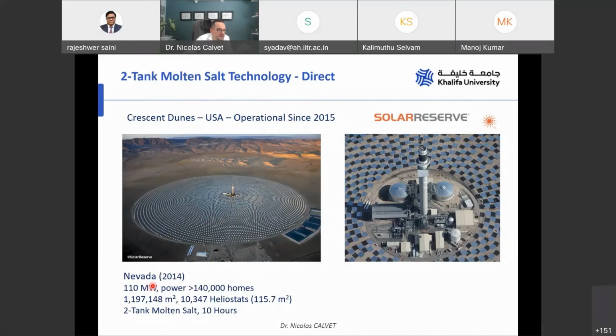I think we have now reached the limit for Power Tower, because if you look at the configuration of the plant, the last heliostat is very far away from the bottom of the tower, maybe more than 1 kilometer, maybe 2 kilometers. And so it's very difficult to concentrate the light very accurately in the receiver.